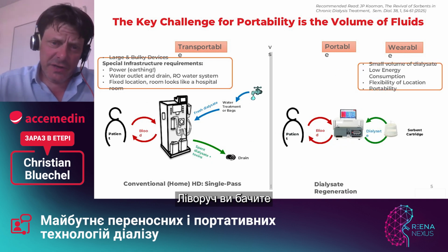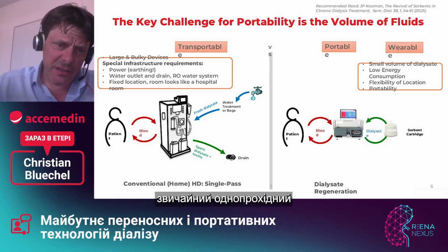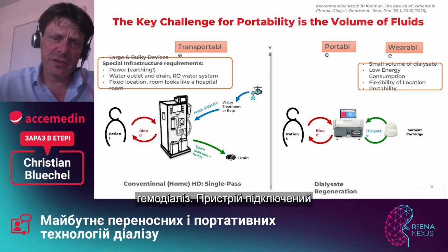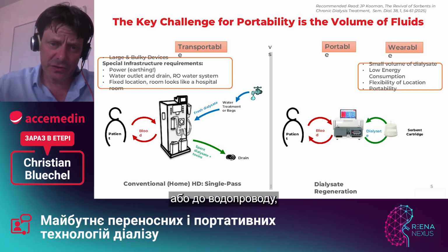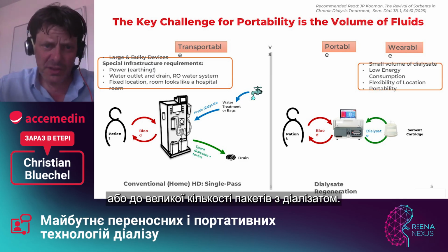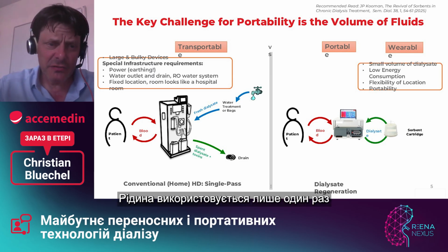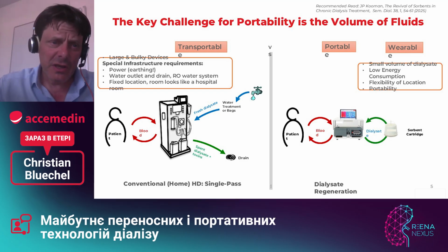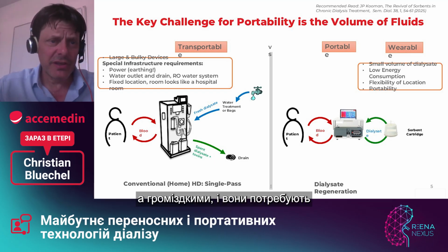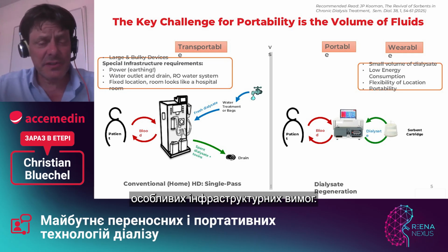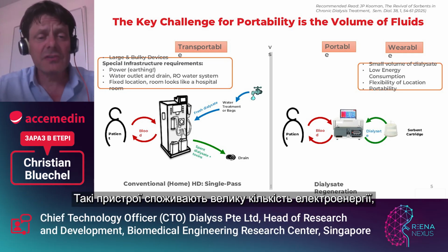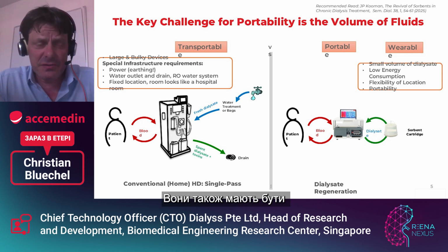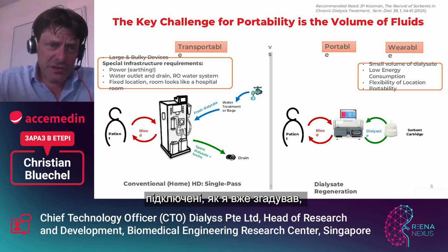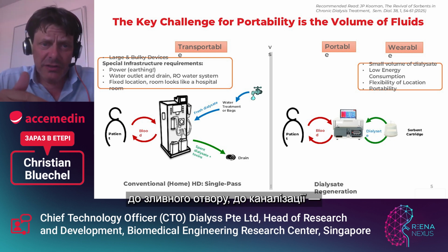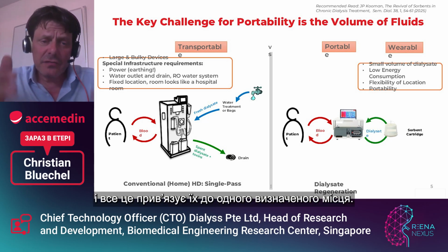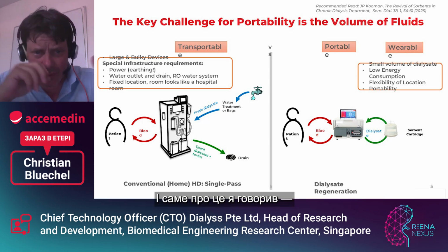The key difference here is on the left side you see a conventional single pass hemodialysis. So the machine is connected to a water outlet or to a large number of bags. Then the fluid is used one single time to treat the patient's blood and goes down the drain. And this makes the machines very large and bulky, and they need quite special infrastructure requirements. They have a very high power requirement because you need to warm up all this fluid that is being used for the treatment. They also need to be connected, as I mentioned already, to a water outlet and to a drain, and all that fixes them to one fixed location.